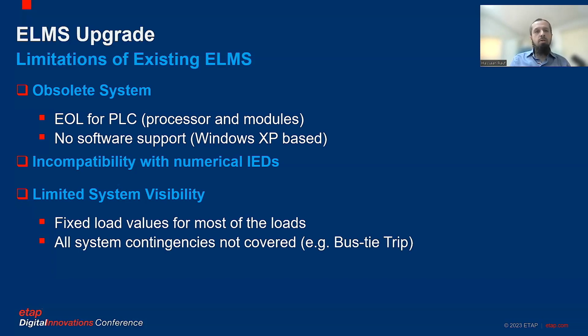Then, all system contingencies were not covered. One example of this is the bus tie trip. If you can recall from the SLD, both the generators are interconnected through the bus ties. So if there is a tripping of bus ties, there was no logic configured to take action against such a trigger or such a contingency.